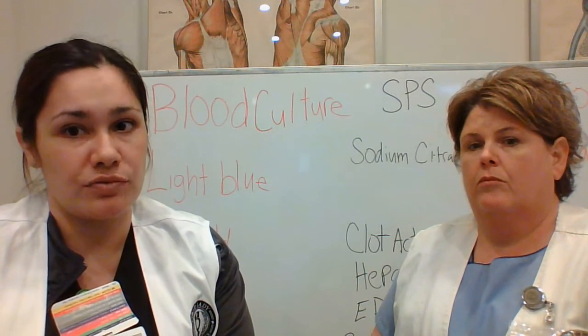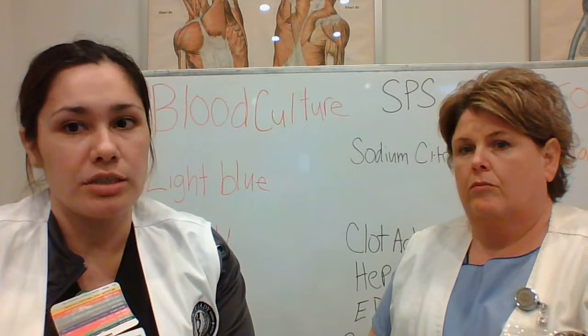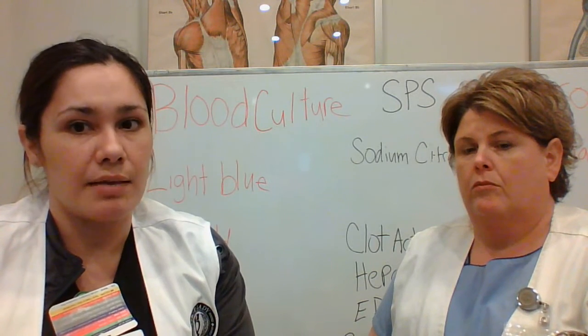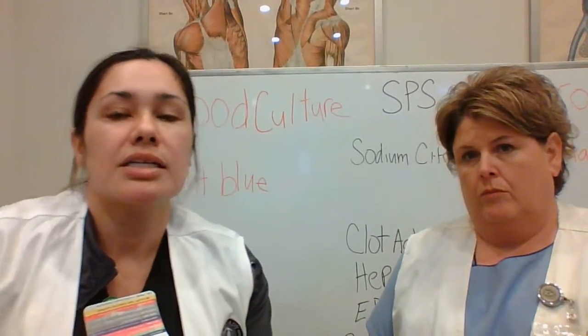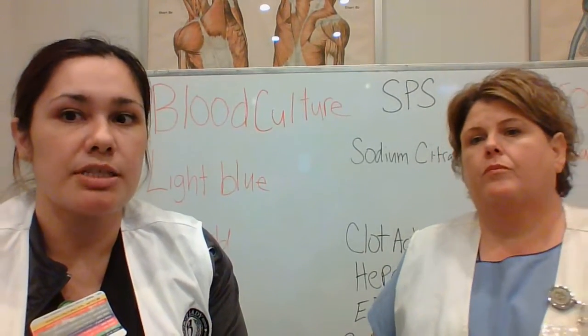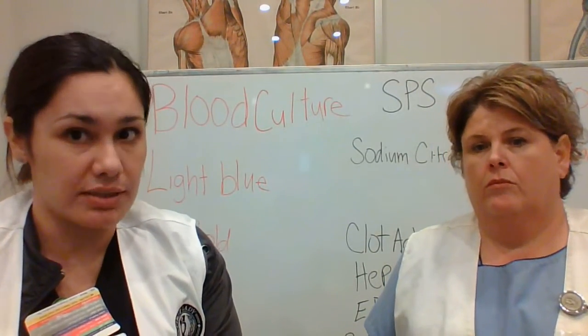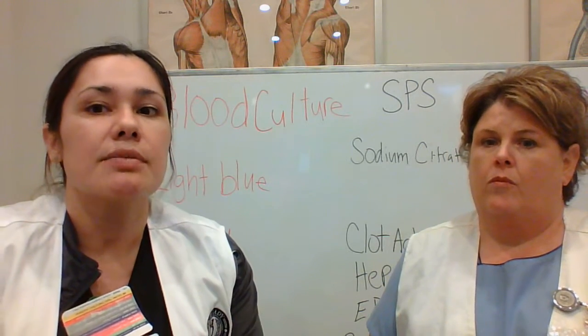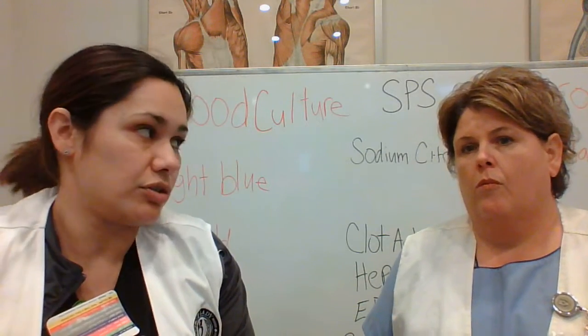Pre-centrifugation or tubes awaiting centrifugation. Stoppers should remain on to prevent inaccurate results and evaporation and contamination. Centrifuge operation. Tubes must be balanced. Equal-sized tubes with equal volumes of specimens must be placed opposite one another with the lid closed. Centrifuging plasma specimens. Plasma specimens may be centrifuged without delay. Centrifuging serum specimens. Serum specimens must be completely clotted before centrifugation. Complete clotting takes 30 to 60 minutes at room temperature. A specimen should never be centrifuged more than once.